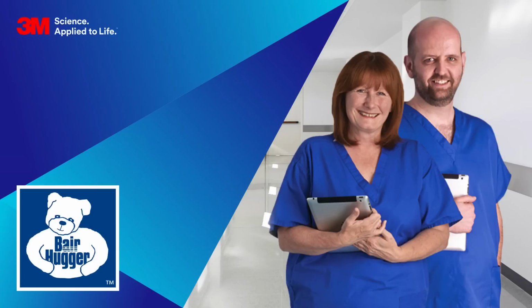Helen, regarding maintenance, how should the temperature management unit be cleaned? It should be cleaned according to your trust policy or hospital policy, but it should be with warm soapy water with a soft cloth or an alcohol-free detergent wipe. Helen, what is the temp in range light? The temperature in range light will come on when the machine is blowing 1.5 degrees or so either side of the selected temperature that you've chosen.